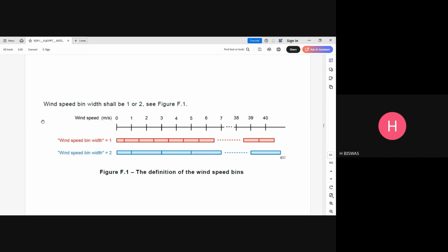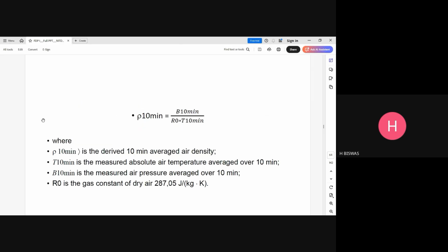So one thing is called binning. Binning means we develop a power curve based on different available wind speeds, but that wind speed has to be measured for certification purposes at a specific interval of 0.5 meters per second. IEC says that to develop a wind curve, we need to follow this binning procedure at 0.5 meters, because for a wind power curve there's the concept of cut-in speed and cut-out speed, and within these two the wind power actually comes into picture.